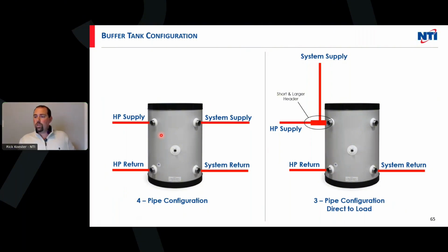Buffer tank, those are some great conversations. When we talk about buffer tank, there's a lot of different ways to pipe them. Mostly we're going to see the 4-pipe as you see here on the left, where we're going to have our supply return from our heat pump. That's one system. And then we're going to have our supply return from the heating system itself inside the home, whether it be radiant, panel rads, fin tube, whatever it may be, totally separate from the heat pump, right? So the heat pump's only mission is to make sure this tank is staying at the temperature that we designed or we set it for.